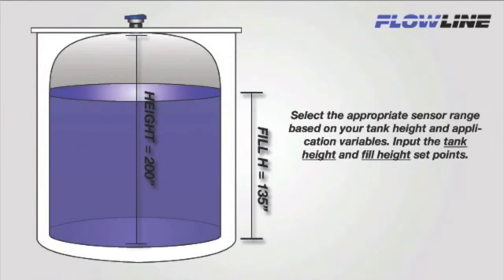So let's put this all together. First, we're going to select a sensor that has an appropriate range based on our tank height and application variables. Second, we're going to input our tank height and fill height set points, which will span our 4 to 20 milliamp output. And third, well, you're done. It's that simple.